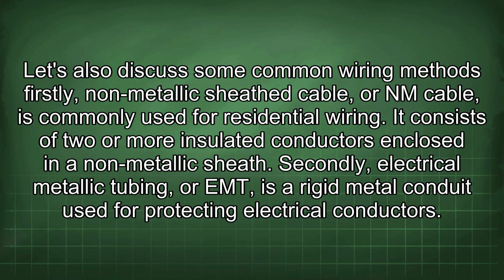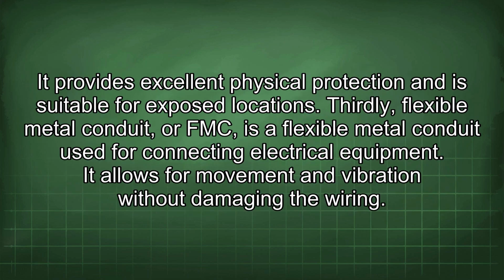Firstly, non-metallic sheathed cable, or NM cable, is commonly used for residential wiring. It consists of 2 or more insulated conductors enclosed in a non-metallic sheath. Secondly, electrical metallic tubing, or EMT, is a rigid metal conduit used for protecting electrical conductors. It provides excellent physical protection and is suitable for exposed locations. Thirdly, flexible metal conduit, or FMC, is a flexible metal conduit used for connecting electrical equipment. It allows for movement and vibration without damaging the wiring.